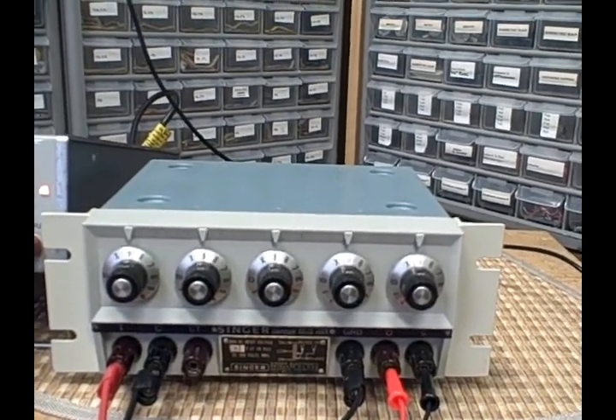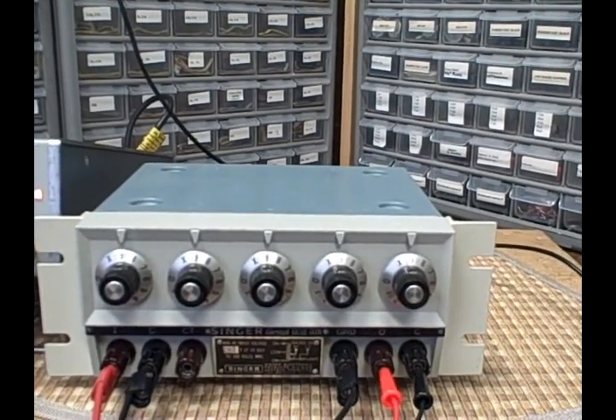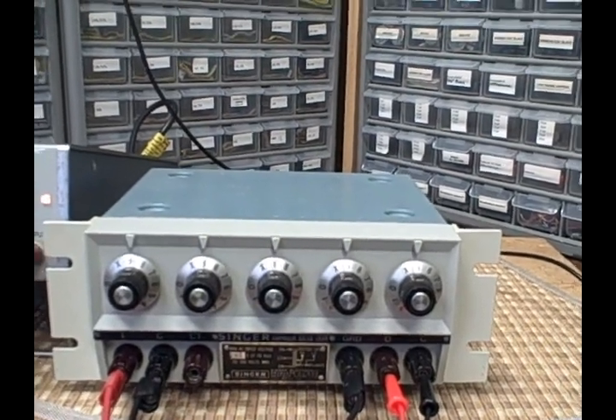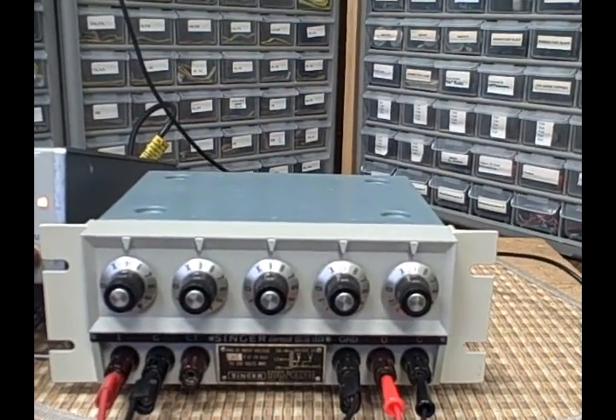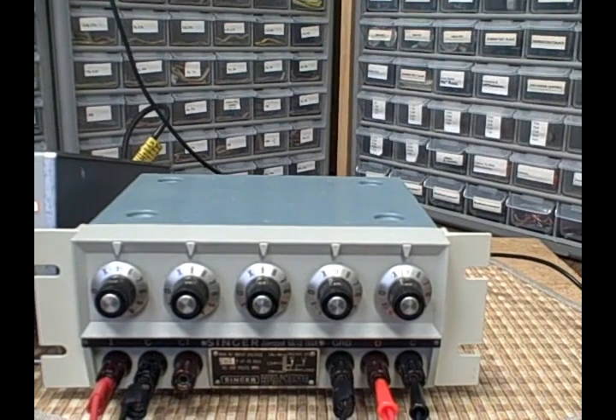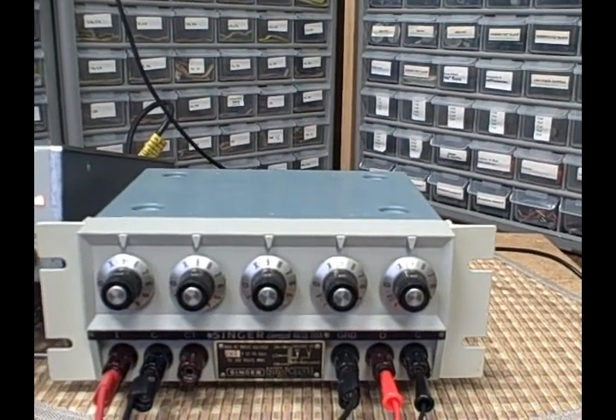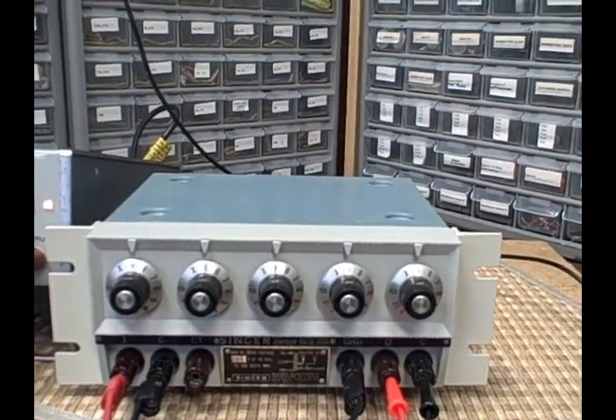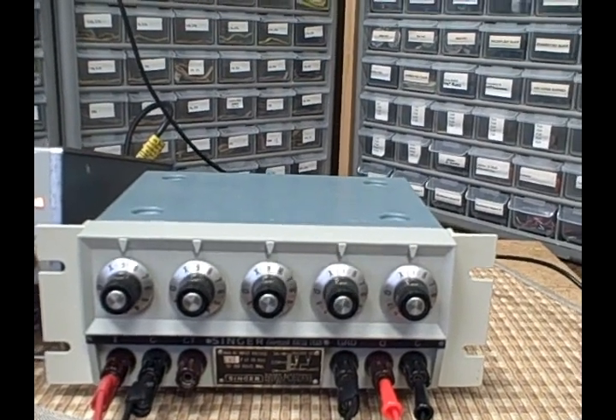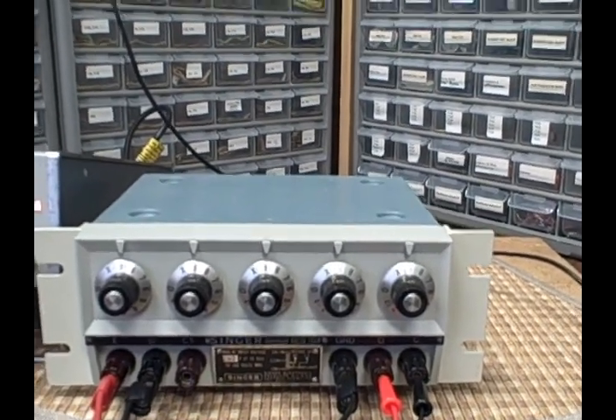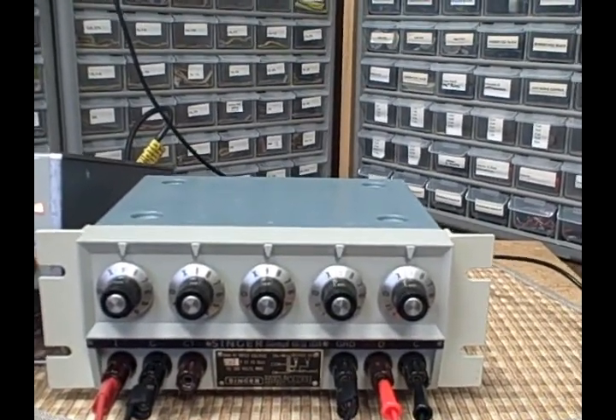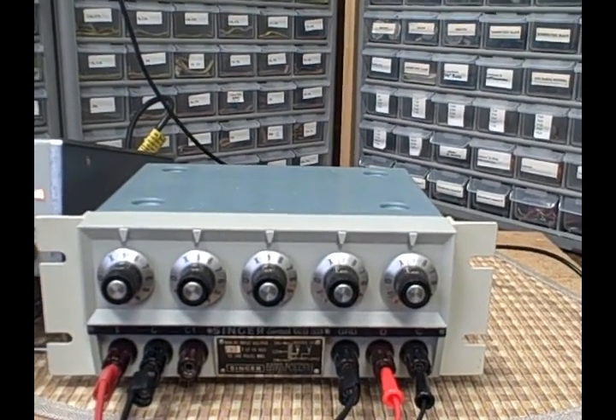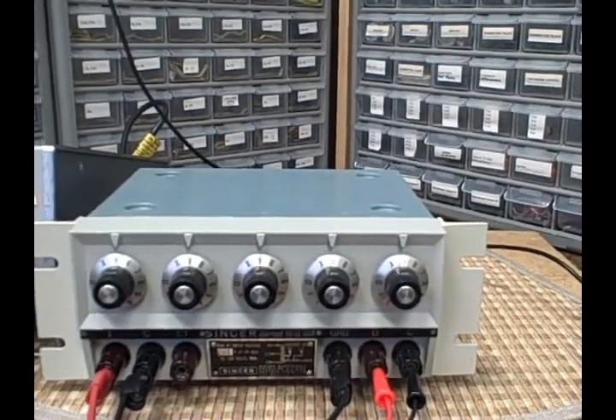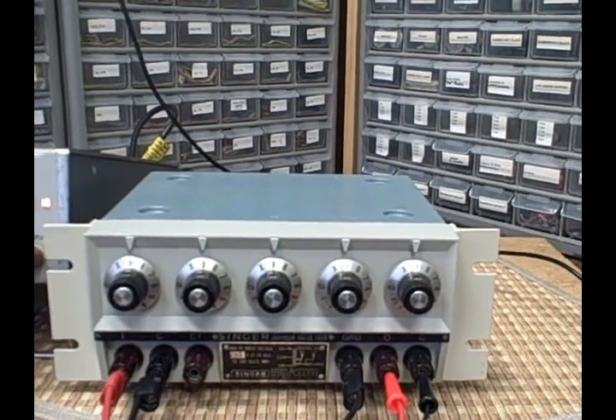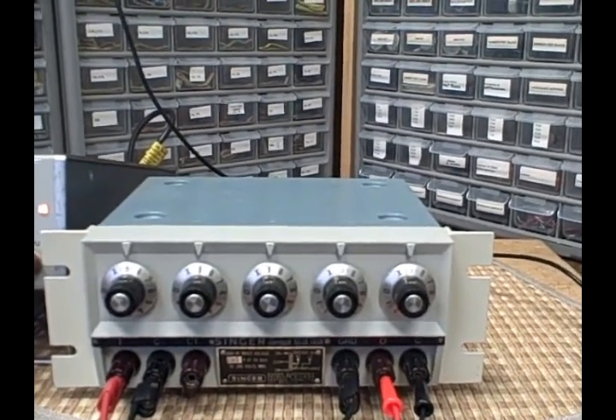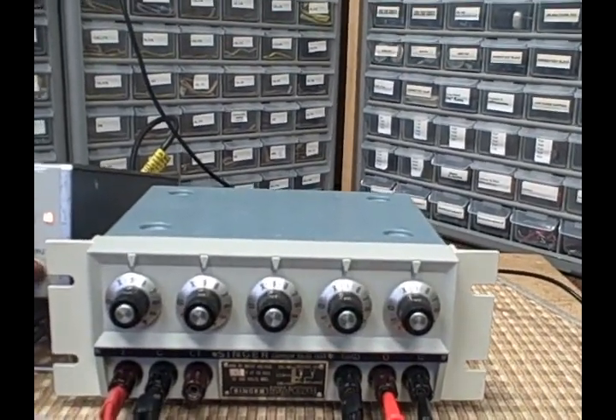The frequency range most often used for maximum accuracy is under 3,000 hertz, say from 60 to 3,000. You can use it up to 10,000, but at a reduced accuracy. It's not a heavily reduced accuracy, maybe a decade, so you're working around 0.01 percent, something like that. Still pretty amazing.